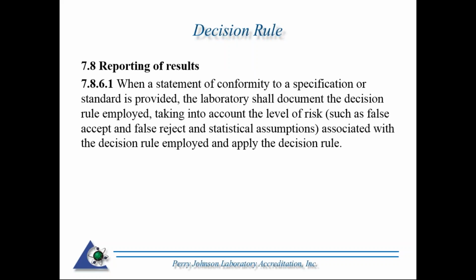And then at the back end, when we're reporting the results, when a statement of conformity to a specification or standard is provided, the laboratory shall document the decision rule applied, taking into account the level of risk, such as false accept and false reject, and statistical assumptions associated with the decision rule employed and applied. So during contract review, we have to define the decision rule, and we also are going to have to be reporting it.